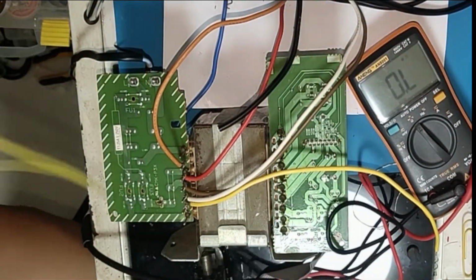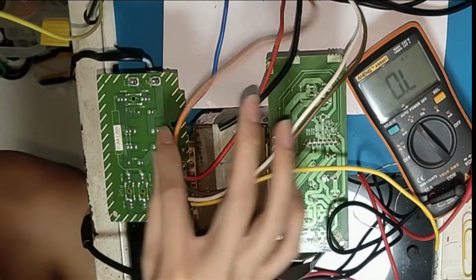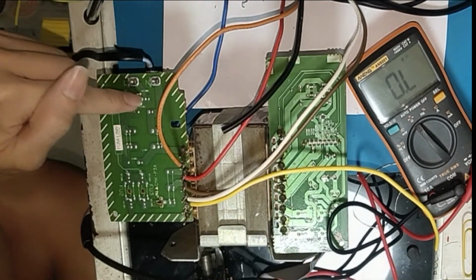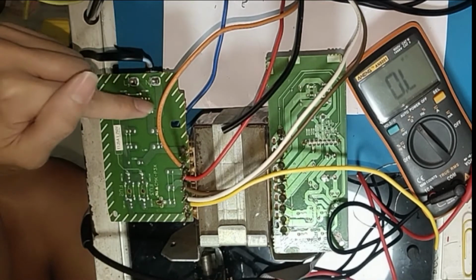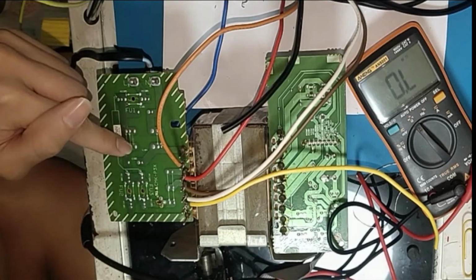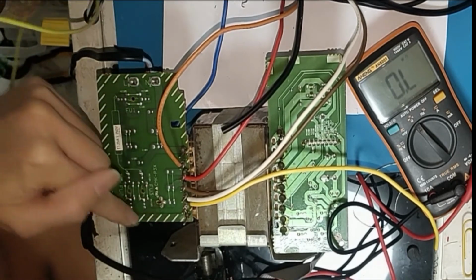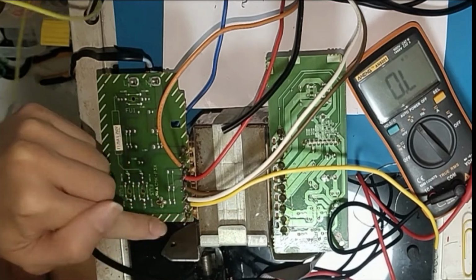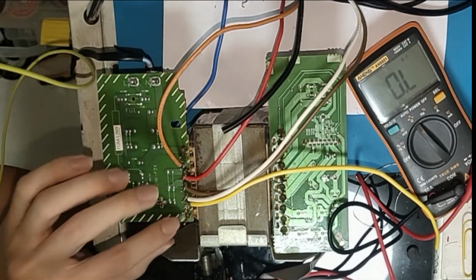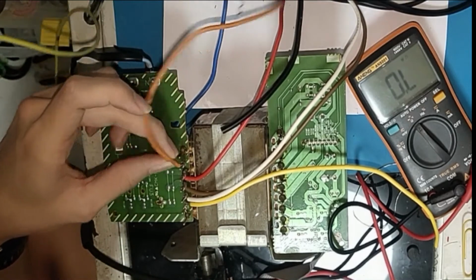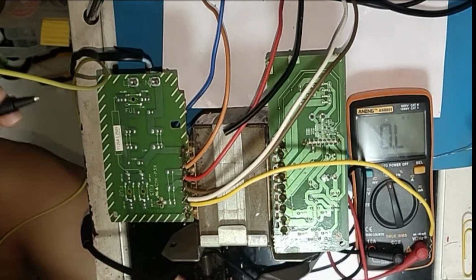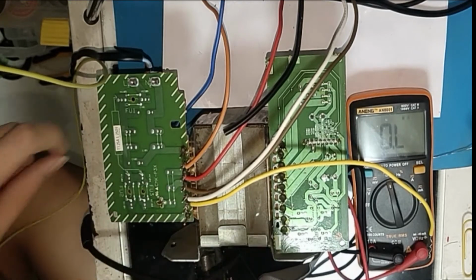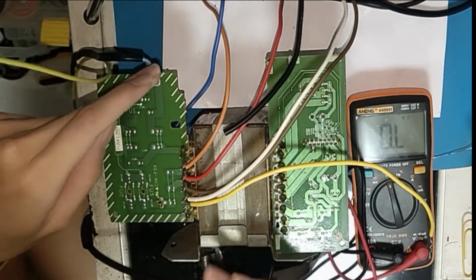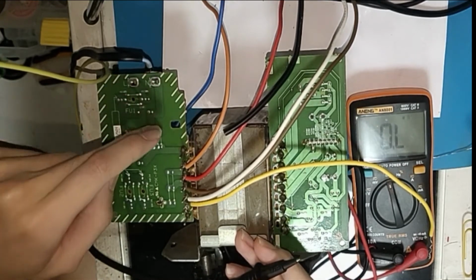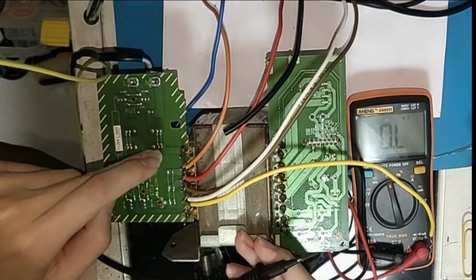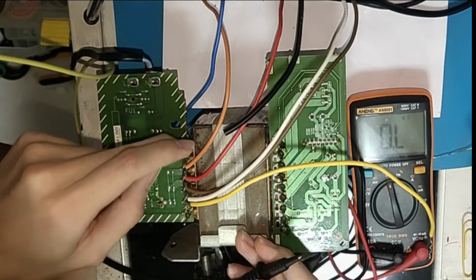As you can see from the trace, current will flow through here, down to there, across the jumper, across the fuse, and into the winding itself. This will be the primary winding of the transformer. That will be one end, and the other end you can trace from here down to there across the jumpers and end up at there.